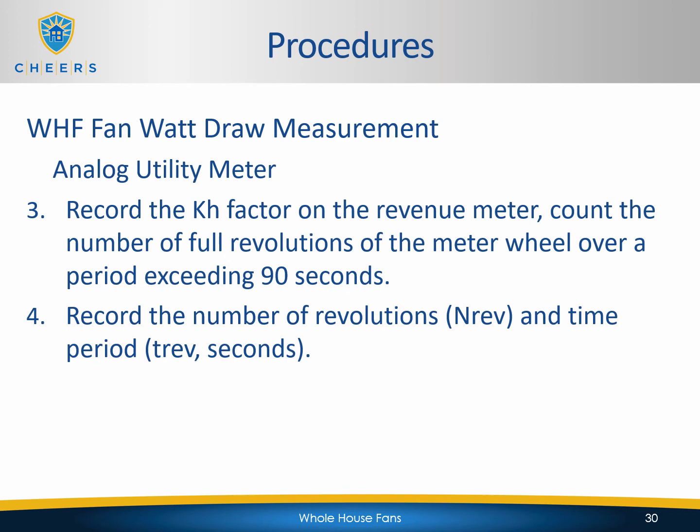You'll need to record the KH factor on the revenue meter, count the number of full revolutions of the meter wheel over a period exceeding 90 seconds, and then record the number of revolutions and time period.